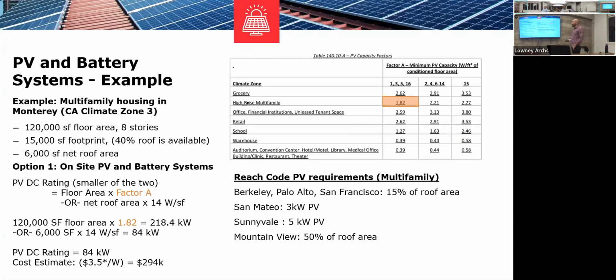So for this building, we started calculating the PV requirement using both formulas. The first one was the floor area times factor A. Since this is a multifamily building, the factor is 1.82 multiplied by the floor area, and we come up with a PV capacity of 218 kW. The next step is to calculate based on the roof area, which is 6,000, what we decided for the net roof area. Multiplied by 14, it comes down to 84 kW for the PV capacity. So out of the two numbers, 84 is the lower. So that's our code required PV capacity.